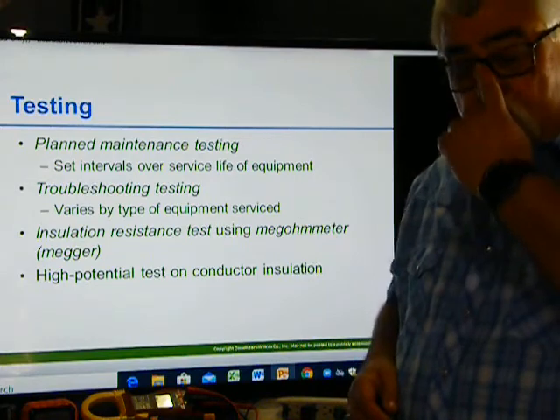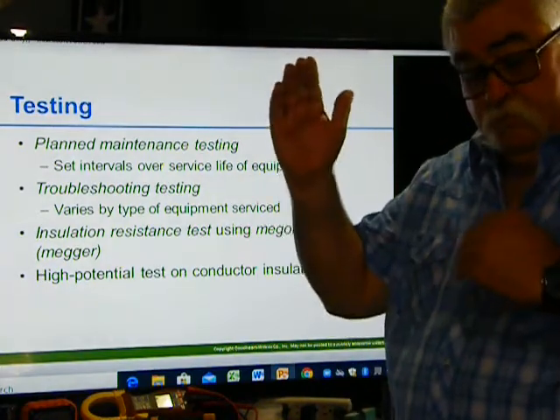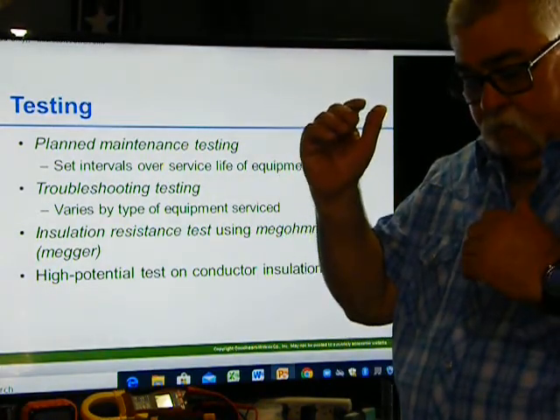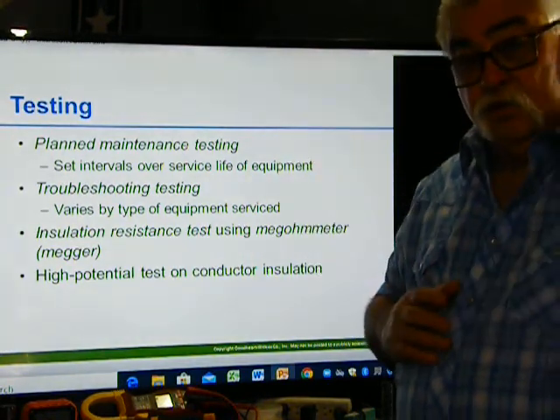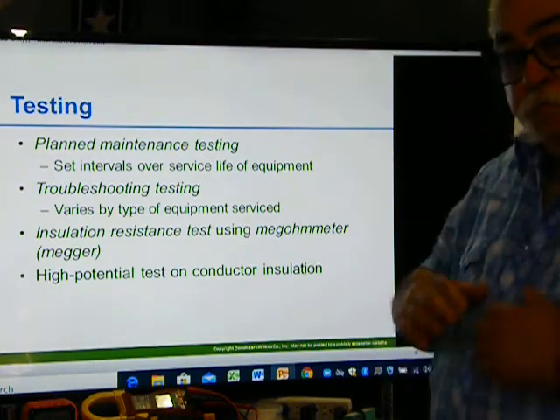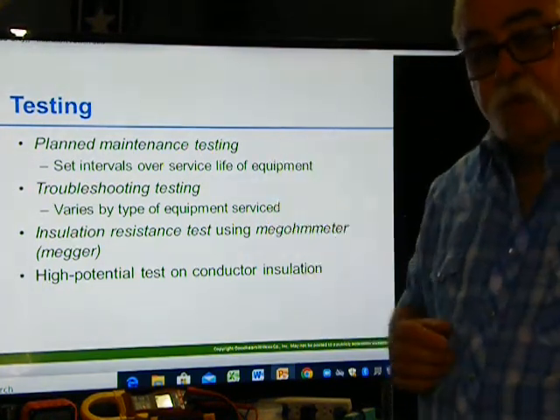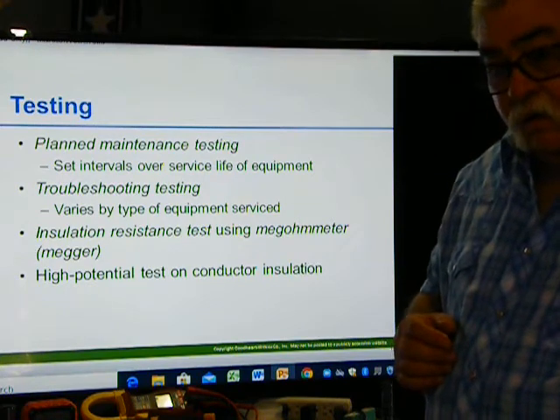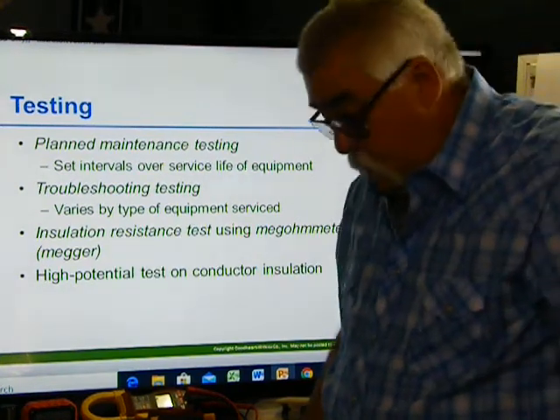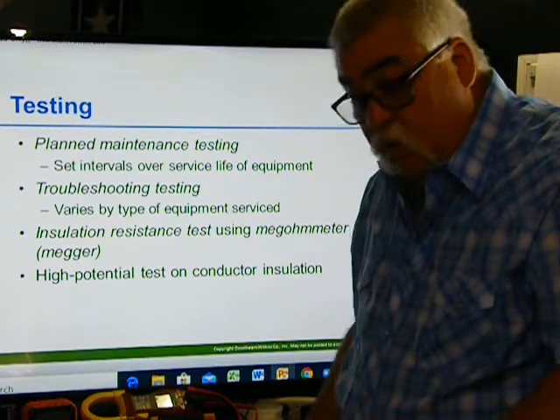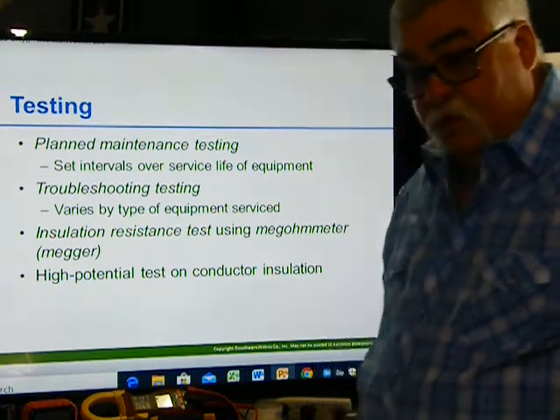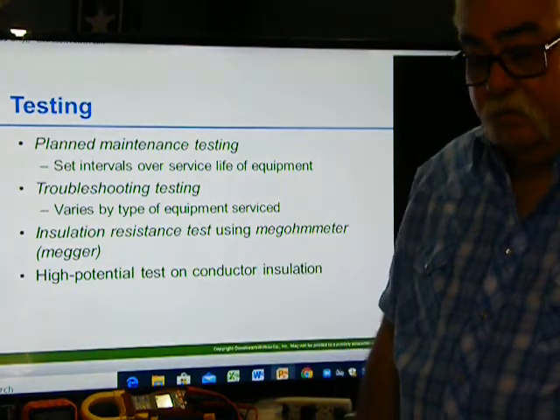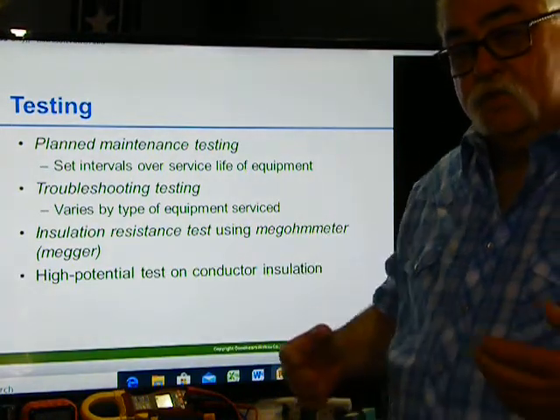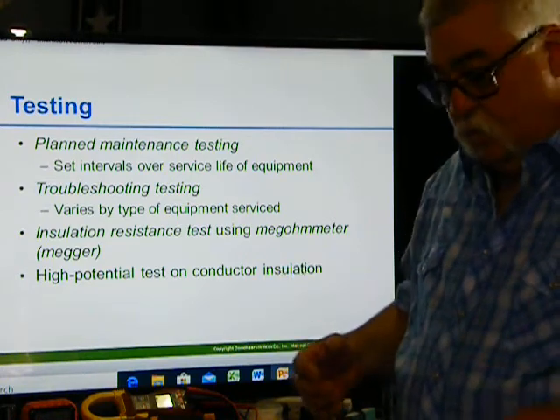So like the one where I showed you where they're making the transformer, and they do a test, a lightning test, that the transformer can handle a lightning strike, because there's going to be spikes. So they're shooting 200,000 volts into a transformer to make sure it can handle it. Same thing you do on an insulation. Some of these older megger makers, they have a crank, and you crank it up and it sends out 1,000 volts on the line. So you have to be very careful. Why? Because you want to see how much of it escapes through the insulation.